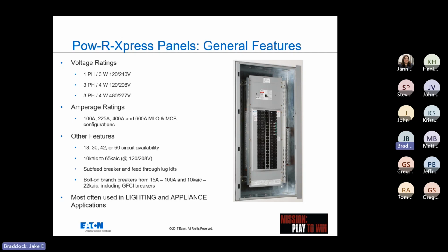And so how this typically would work for a panel, again, this is probably the most important piece of the Pow-R-Xpress program, is Shaler would have the box itself, the trim itself, the interior itself, all as separate components on their shelves, and they have various main breaker and main lug kits available, as well as various branch breakers. So depending on what panel you actually need, they can pull all those various components straight off of their shelves and supply them to you, and you can just put it all together, and then you have the panel you need in the field same day.